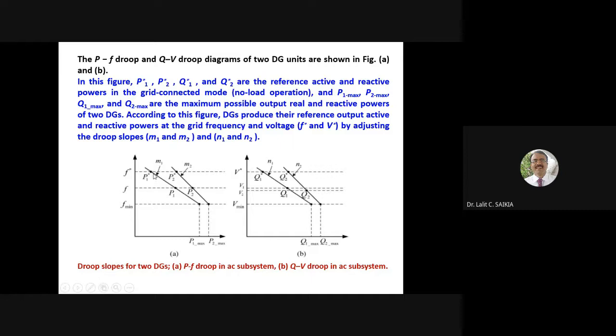So power shared by unit 1, DG1, and DG2 — this is the reactive power shared by DG1, and this is the reactive power shared by DG2. Now there is a limit on this P and Q: P1 max, P2 max represent the maximum possible output of real and reactive power.